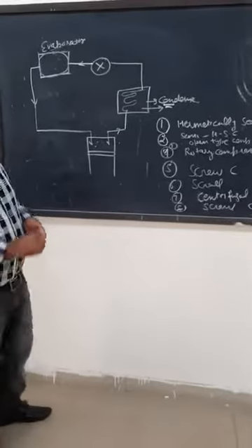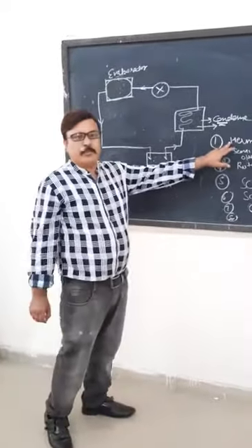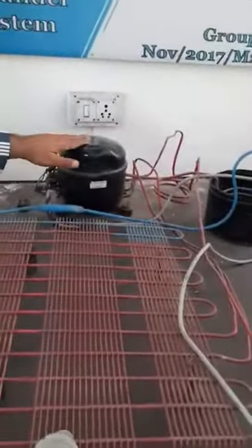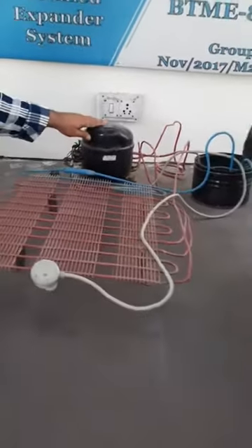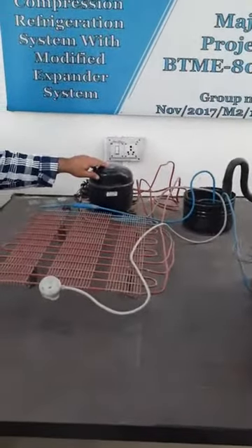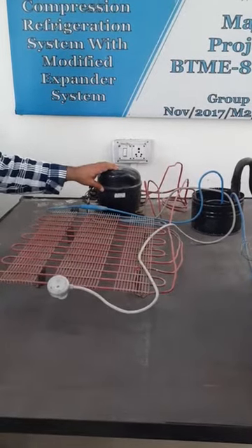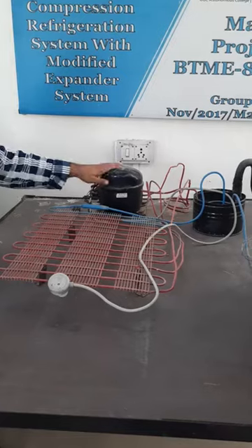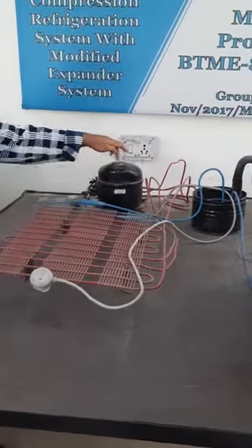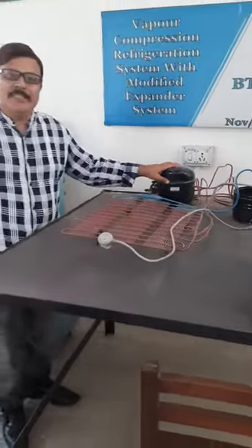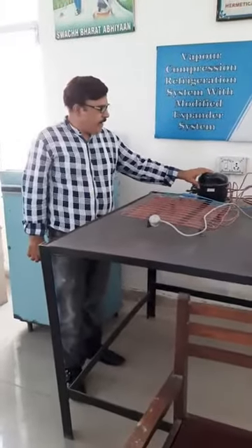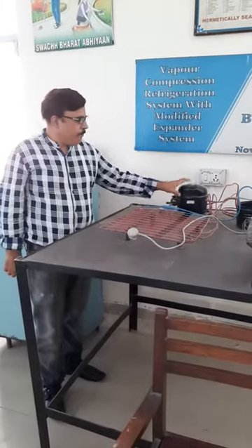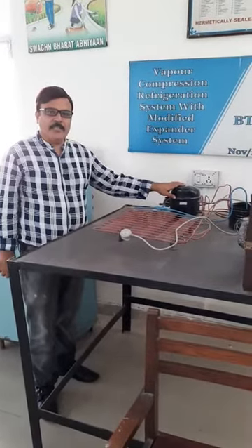First of all, we have the reciprocating hermetically sealed type compressor. Look at here. This is called the hermetically sealed type compressor. This is the dome under which both the motor and the compressor are placed inside a single dome, and the upper and lower parts are welded. It is very compact in size. There is no leakage problem and there is less vibration, but it has one disadvantage.